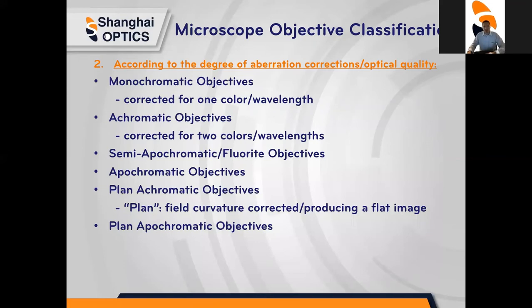According to the degree of aberration corrections and optical quality, an objective may also be classified according to the degree of aberration corrections and optical quality, which includes monochromatic, achromatic, and apochromatic objectives. Monochromatic objective is only corrected for one color and wavelength, whereas achromatic objective is for two colors and wavelengths. The apochromatic objective is corrected for a broad wavelength range, and it is vital so you have the highest quality image.